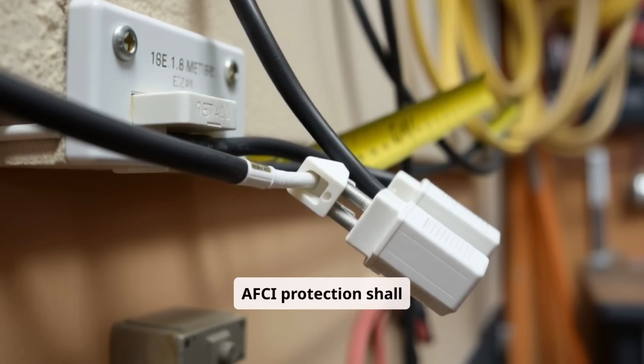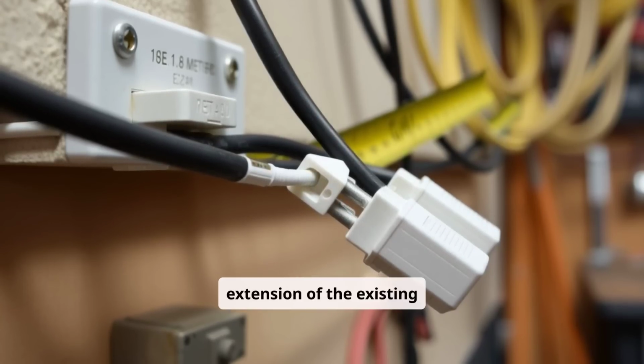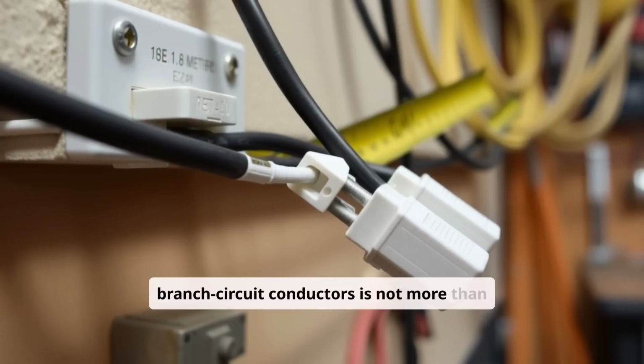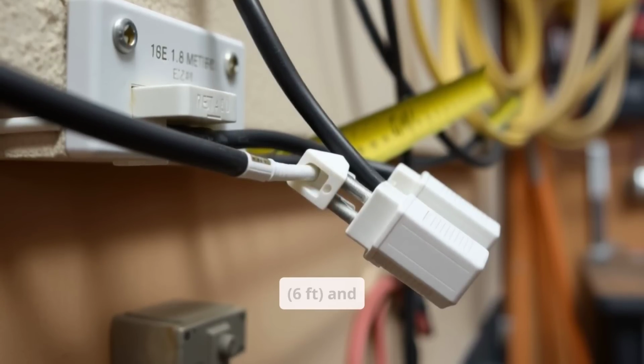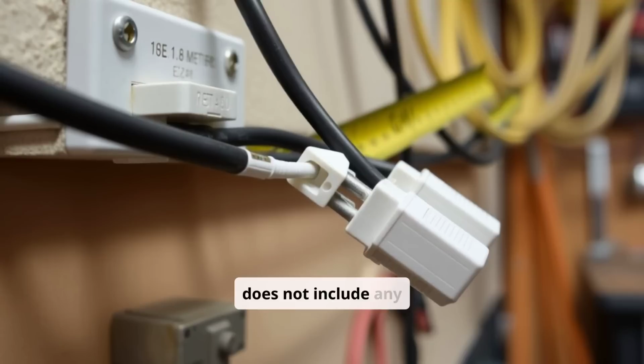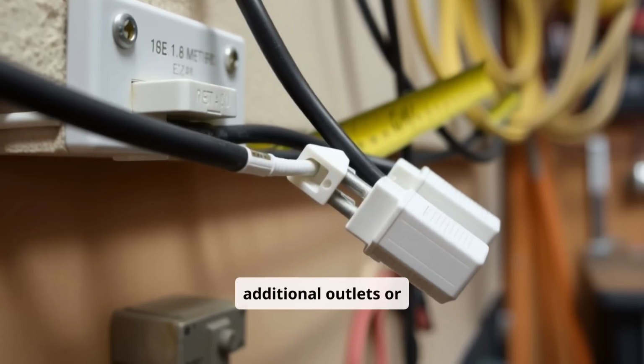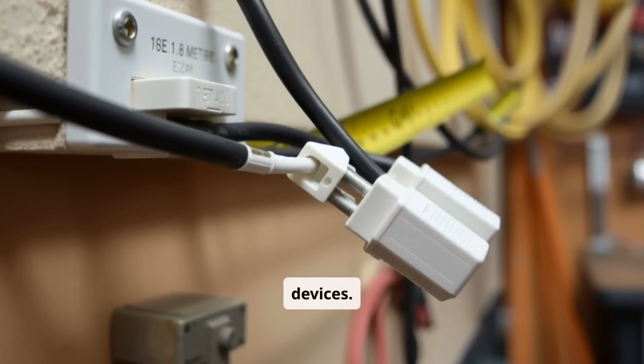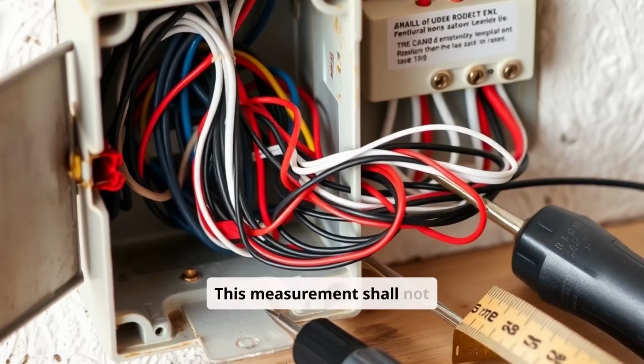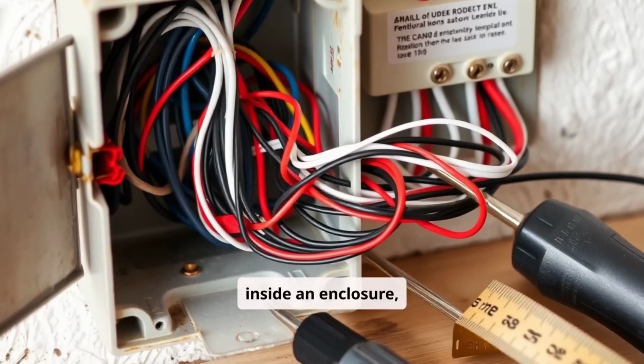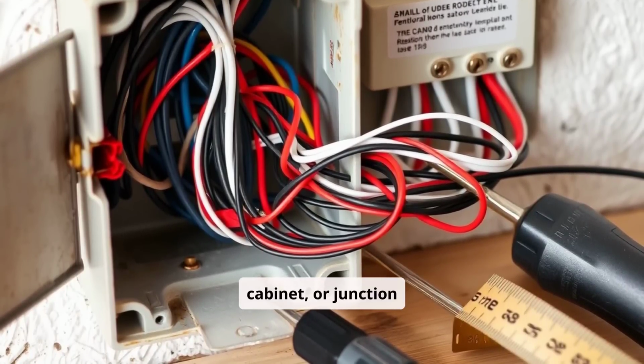Exception: AFCI protection shall not be required where the extension of the existing branch circuit conductors is not more than 1.8 meters (6 feet) and does not include any additional outlets or devices, other than splicing devices. This measurement shall not include the conductors inside an enclosure, cabinet, or junction box.